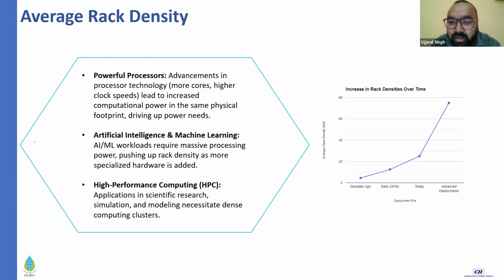This is the typical rack densities. Earlier we were used to operating around 5 to 10 kilowatts. In the early 2010s we went up to 15. Today we operate on average between 20 to 40, and some of the AI processes, for example if you are driving a Tesla car, need a lot more decisions to be made in a fraction of a second, identifying the traffic, identifying the people walking nearby, identifying stray dogs, identifying people braking immediately in front of you, where the road is curving in, etc. So they require very high processing loads, and they'll be using some 80 kilowatt or 100 kilowatt density systems for their individual processing.